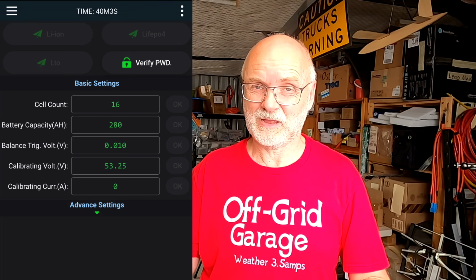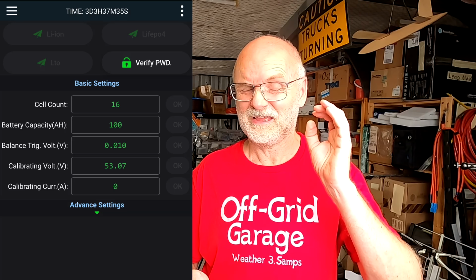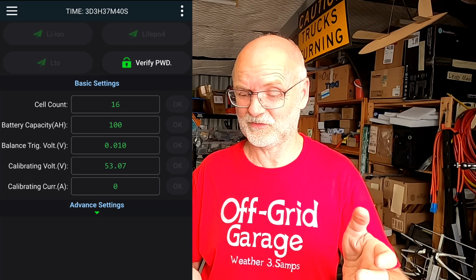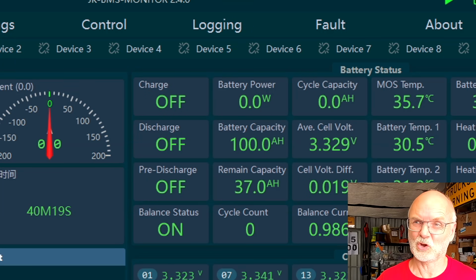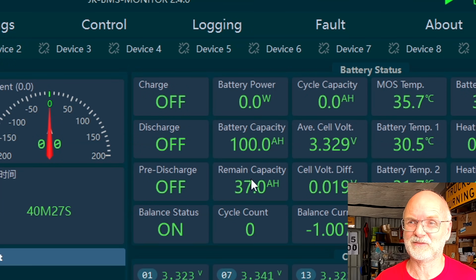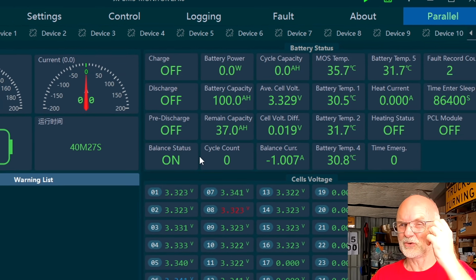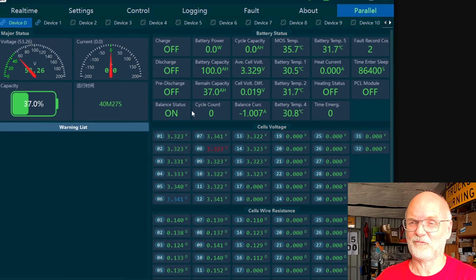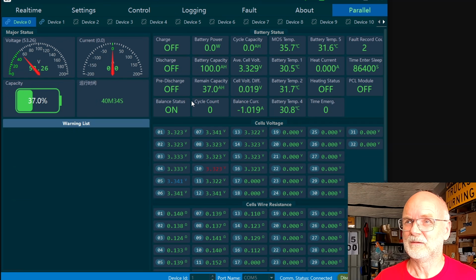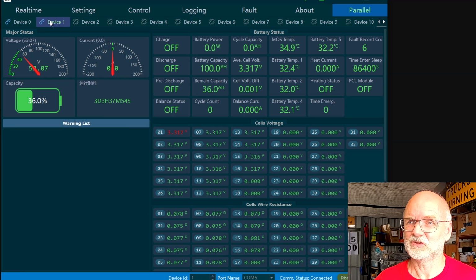Master BMS sits on 280 ampere hours. See, 280 ampere hours. So if you go back to the slave, it sits on 100 ampere hours. So it does the calculation correctly, it submits the data correctly to the Victron system or to your inverter, but it shows it incorrectly here in the PC software. Maybe we shouldn't use this stupid PC software anymore because it's just not working. We use it for upgrading to a new firmware and that's it. Forget about the PC software. It is stupid. Totally stupid.